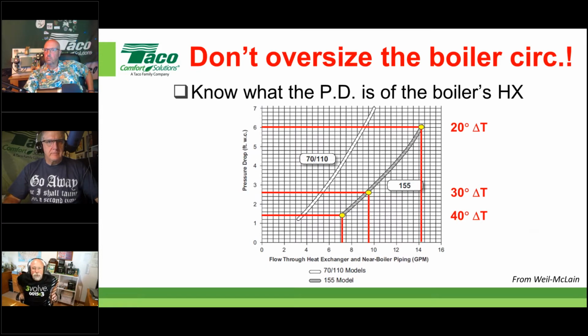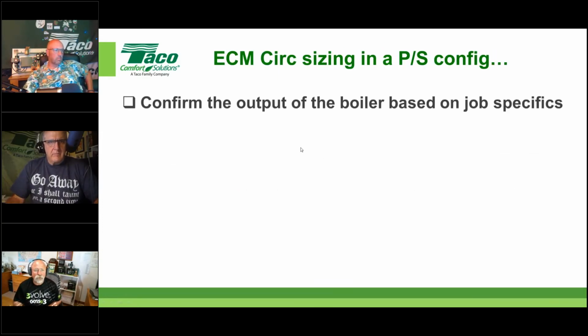representative of a fire tube heat exchanger. If you're using a water tube style, the pressure drops will be a little higher, but it's all the same information. This is all good information you can use on any style of heat exchanger. But when we're talking about fire tube heat exchangers, these are buckets of water. You don't have to do a lot to get any flow through them. Many of them will have minimum flow requirements, so as I showed you on the one document, check with the manufacturer on that as well, okay? So, the sizing of an ECM. Now, the boiler manufacturer just gave you a lot of information.